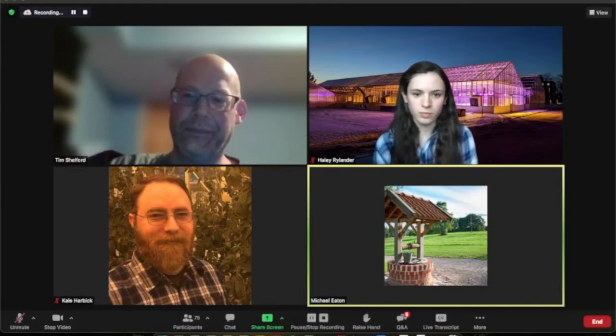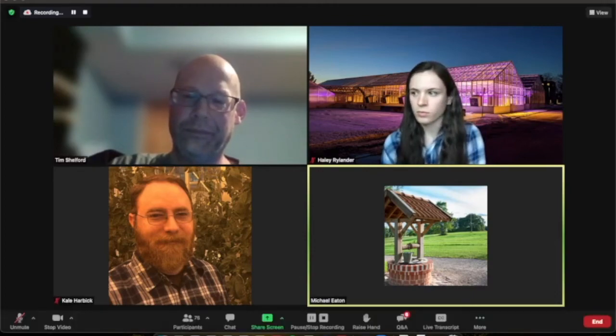Yeah, sure. I'll start. Thanks, Kale. Well, I think some future research at Cornell for the work that I presented on could be examining trade-offs between certain design configurations. For example, if you use an airside economizer, you might not want to supplement with CO2 because at that point you don't have a closed system, and you might run through CO2 much quicker than you want to, which could be costly. So examining interesting trade-offs in design options, as well as looking at trade-offs in investment for lighting efficiency.